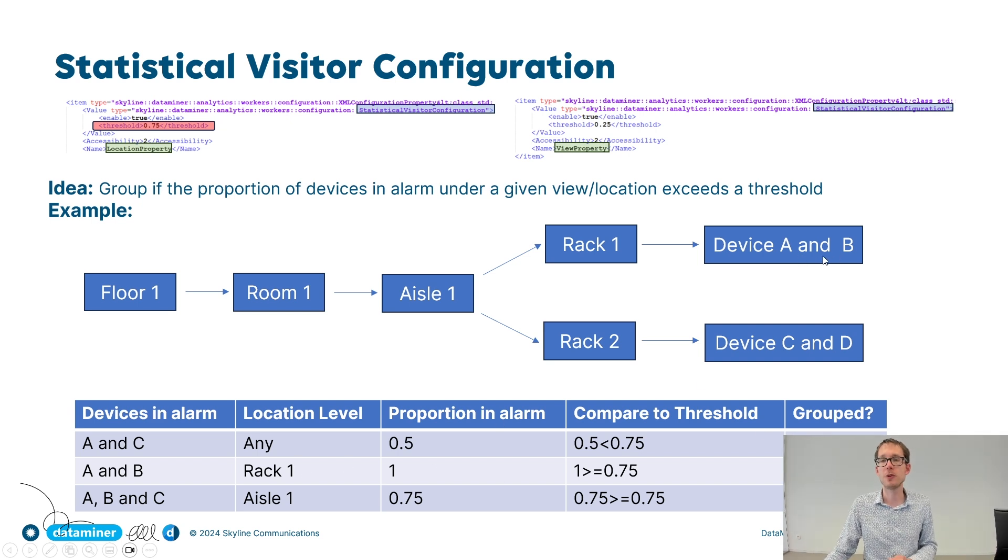Finally, what if we have alarms on A, B and C? Well, in that case, 75% of the devices under aisle one have alarms. And 75% of course is greater or equal to this configured threshold. So again, we will group the alarms. That's the idea behind statistical grouping.